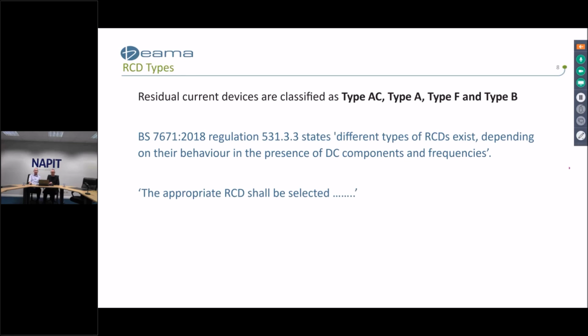The relevant regulation being Regulation 531.3.3, and that requires that the appropriate RCD be selected from Type AC, Type A, Type F, or Type B. So it is quite a significant change within the regulations. These were not listed in previous versions of the regulations.